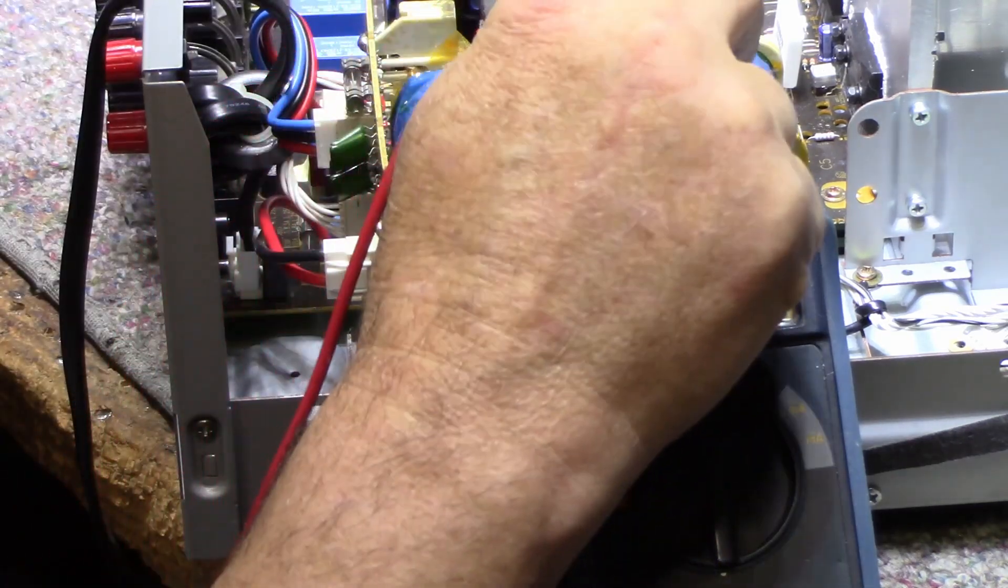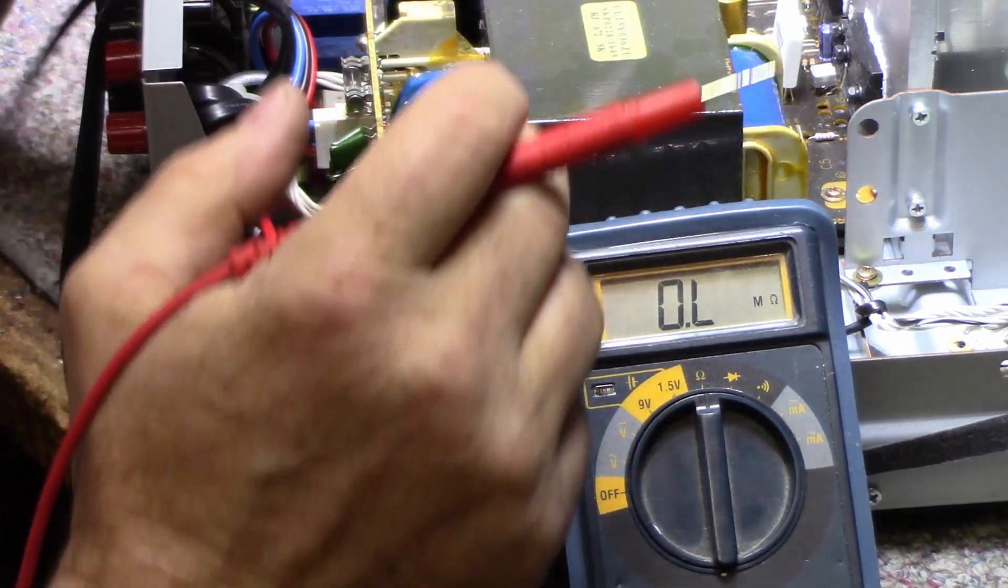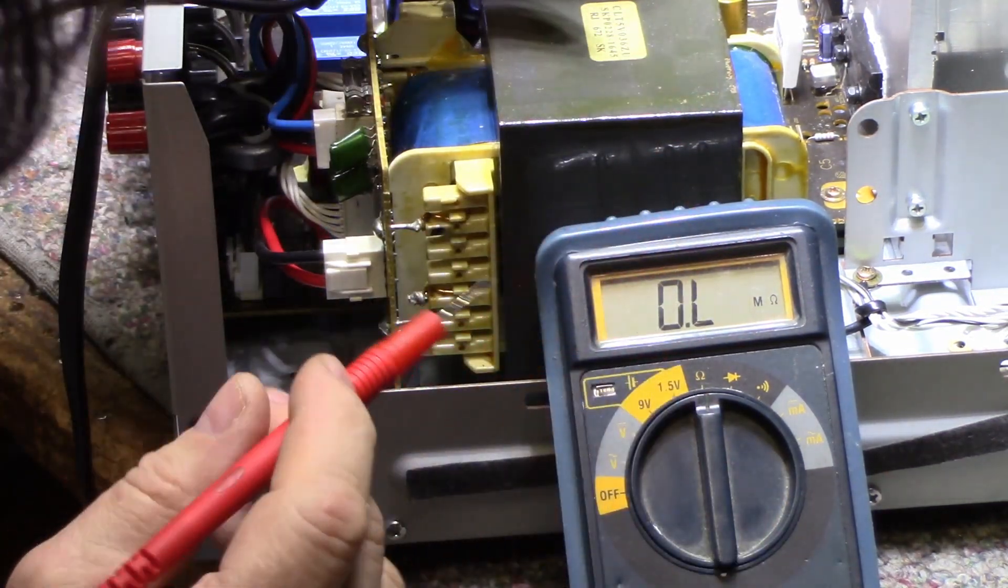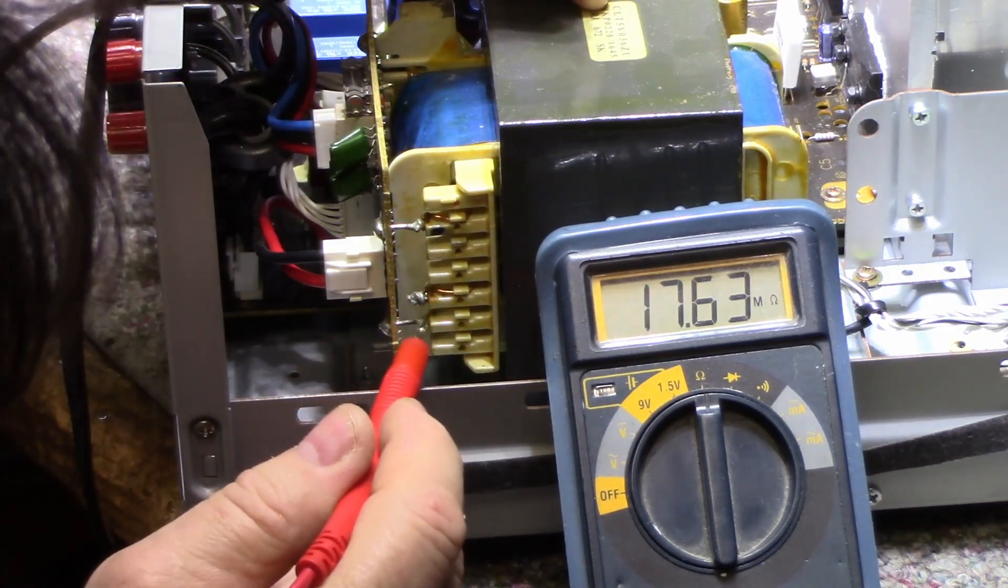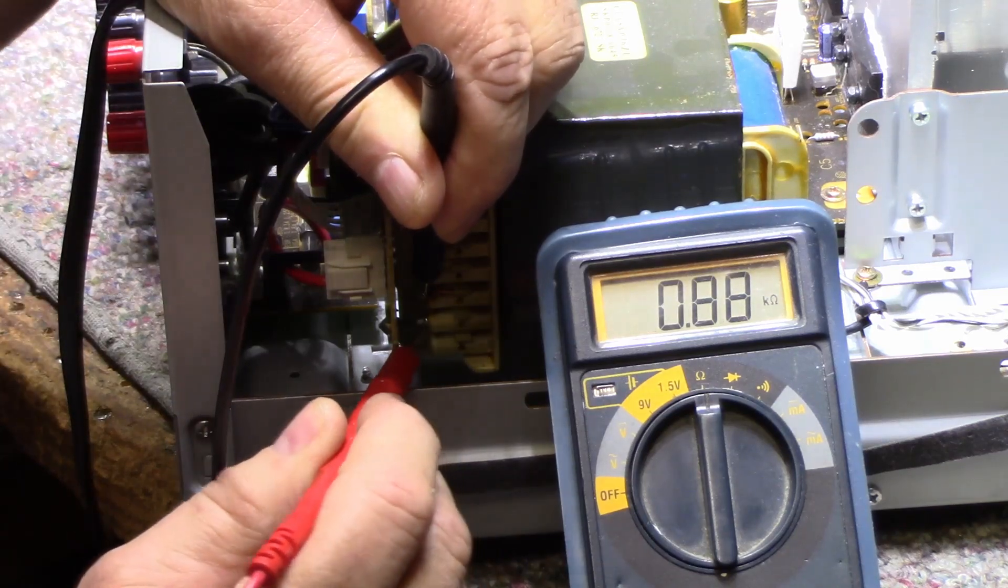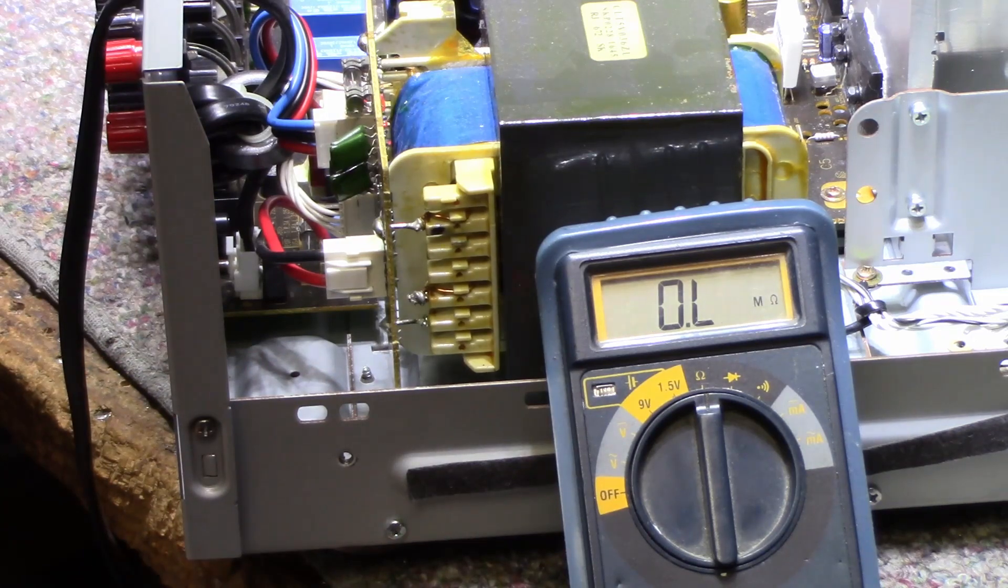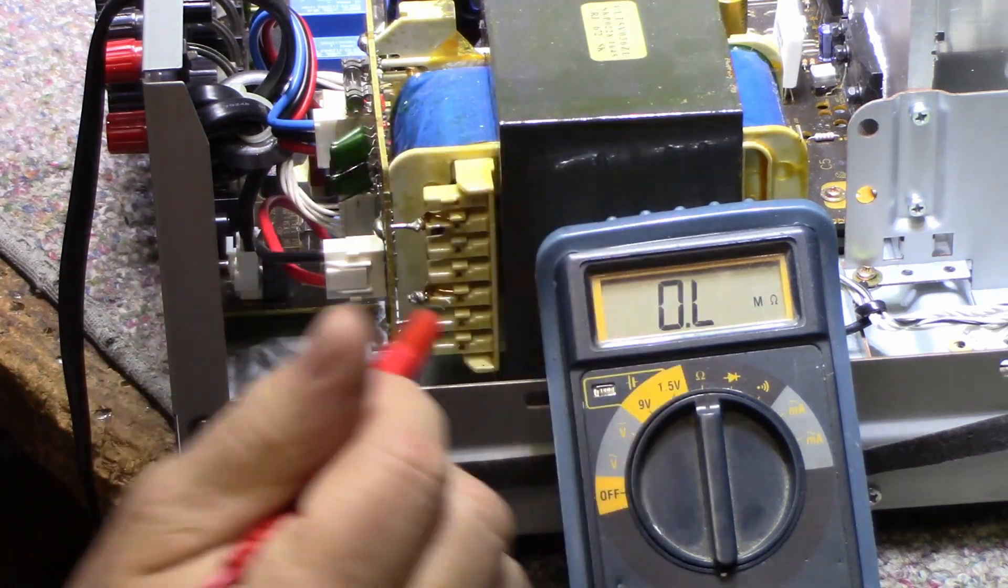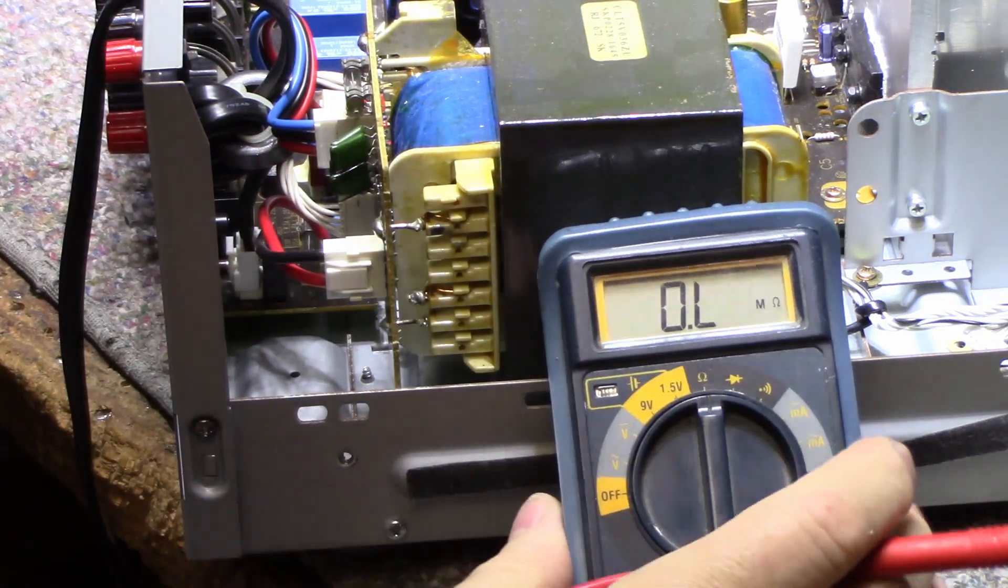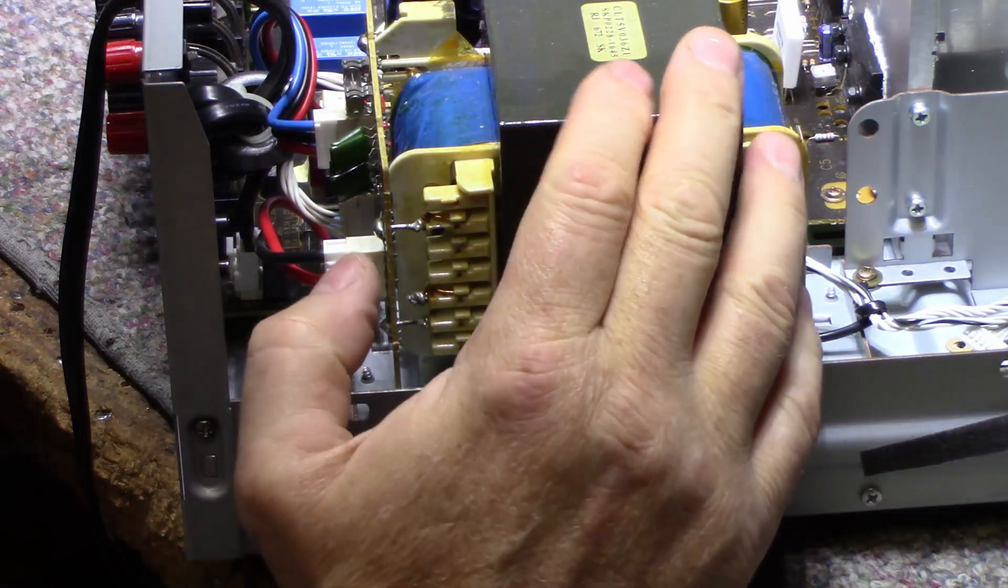You can't really replace the thermal fuse without taking the transformer completely apart. To do that, you would need to cut the welds on both sides, take the laminations, and then you're able to separate the secondary from primary. It's a big job, but you can do it. Another thing is you could bridge this here if this is open, but you're also taking the risk—it's a fire hazard because that thermal fuse is there to protect these windings from overheating.